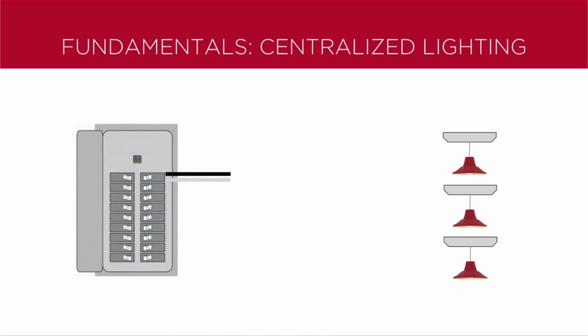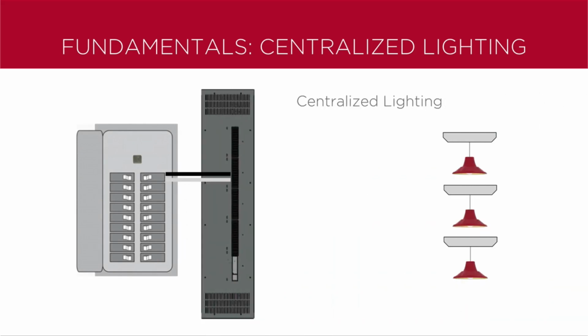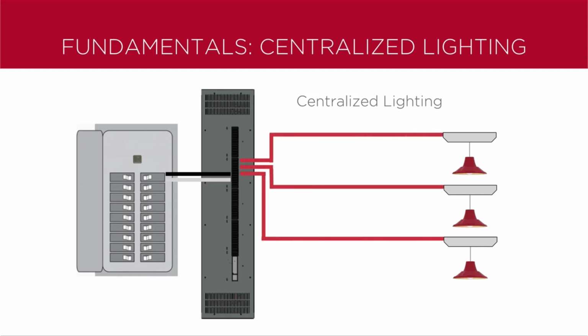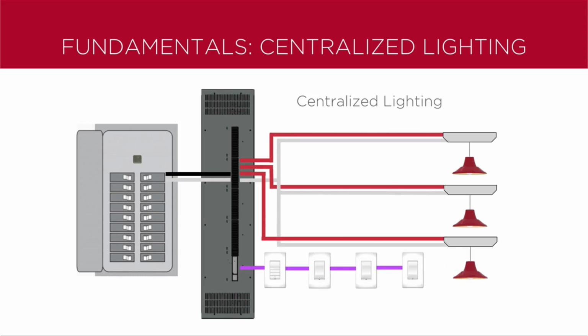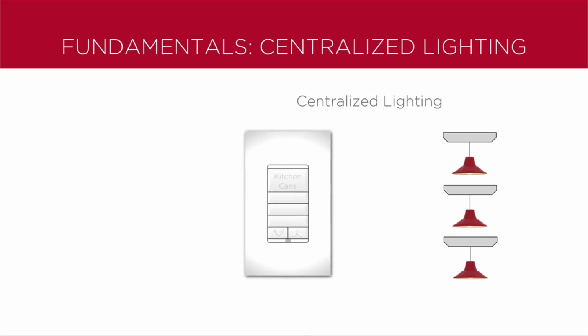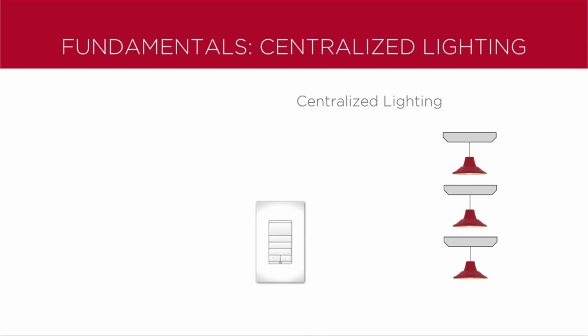In centralized lighting, the circuit breaker is wired to a module in the centralized lighting panel. The dimmer module is then wired to the load. Single, multi-button keypads can control multiple loads or lighting scenes. For your customers, the main benefit of centralized lighting is a reduced number of light switches in each room.